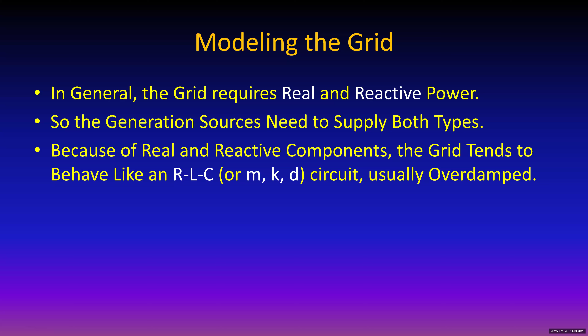There are lots of computer programs that model the performance of the grid, and when you want to put a big PV system on, you generally do a grid study to see how the grid is going to react to this PV system. If, for example, a big cloud comes over the PV system and output drops out fairly quickly, what's that going to do to the stability of the grid? So it's not just about providing the power, but providing it without creating an unstable situation due to things happening too fast. That's part of the challenge here.